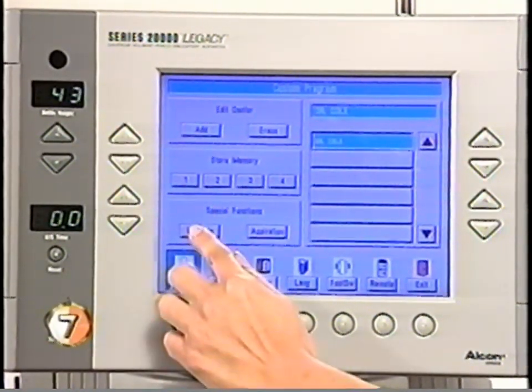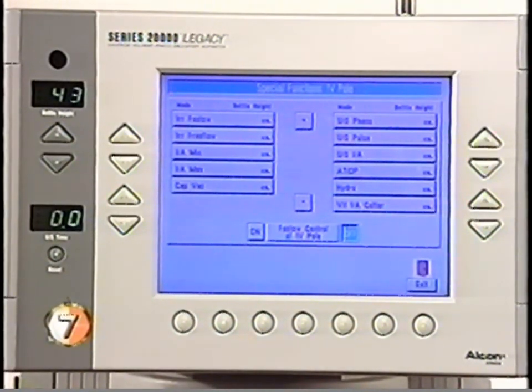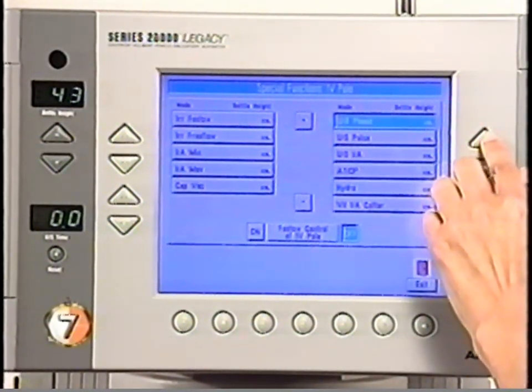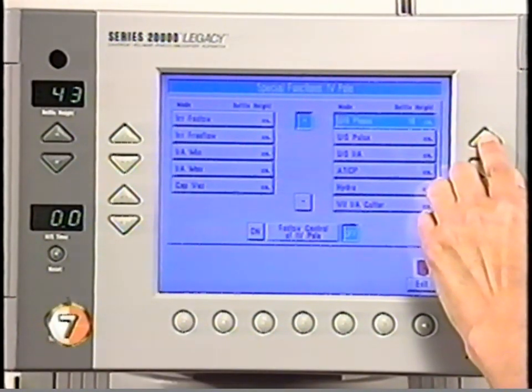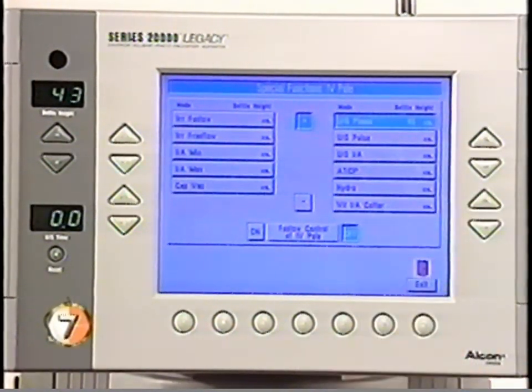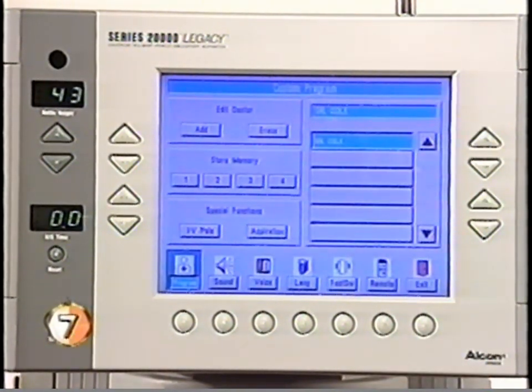Press the IV pole button to customize bottle heights for individual modes on this screen. Select a submode and adjust settings by pressing the plus and minus boxes or any up-down arrows on the front panel. Finally, press Exit to return to the program screen. When no value is programmed in a given mode, the IV pole will remain at the default height of 65 centimeters or at the last programmed bottle height. Alcon recommends that if you program one bottle height within a mode, bottle heights should be programmed for all modes.